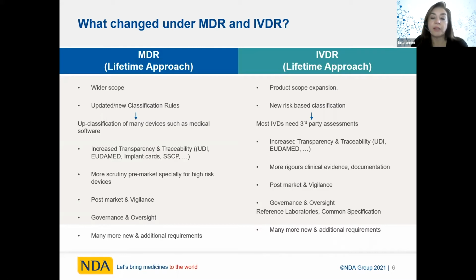MDR has introduced new classification rules, resulting in an up-classification of several devices. One major change is on software, which are now put into higher risk category devices. Not all of them, but most of them. IVDR has also introduced a new risk-based classification. On the current IVD directive, most of IVDs can be self-declared and do not need third-party assessment. However, on the IVDR, about 80 to 90% of IVDs now need to be certified by notified bodies before they can be placed on the market.